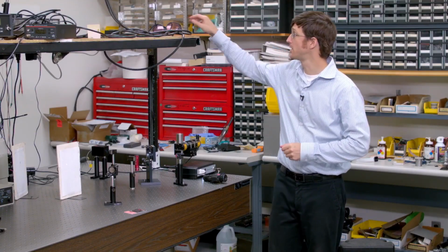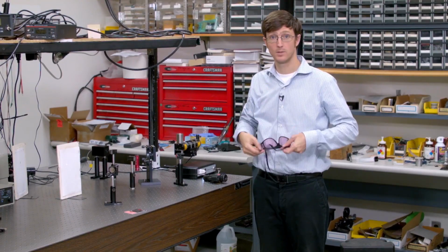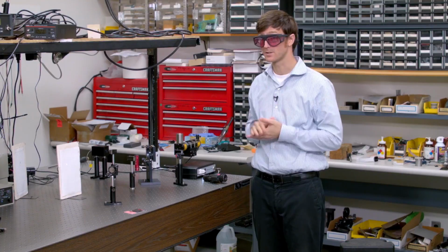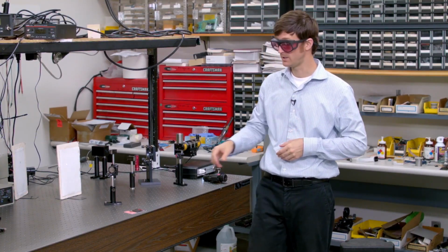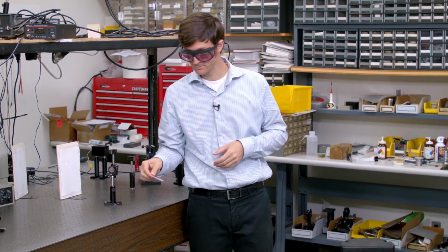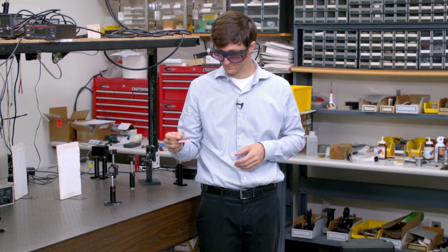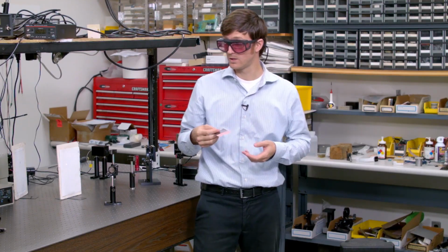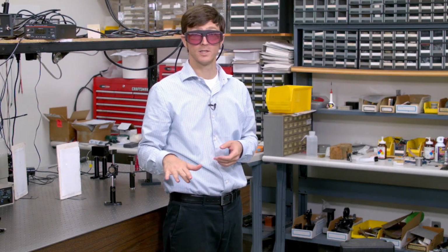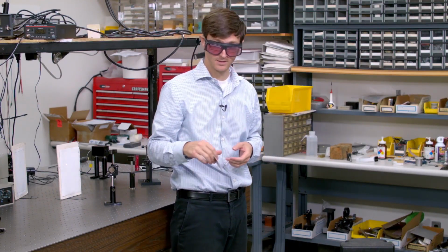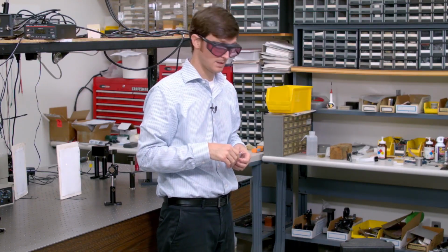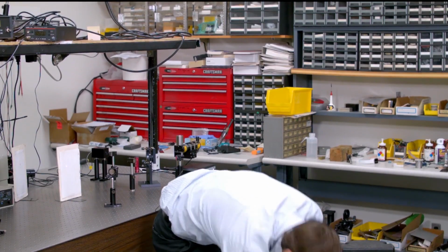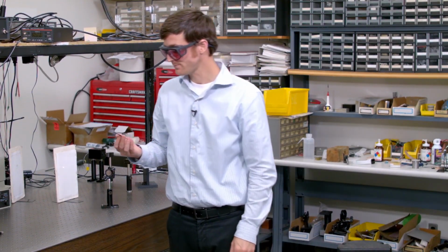So now we need to put on the goggles and repeat the process with a higher powered laser. Now because this is an invisible laser, we can't use an index card to trace the beam. Instead, we need to use an IR card. Whoops. This leads me to another point. When bending over, your eyes might cross the level of the laser beam. So it's a good idea to turn your back to the table and close your eyes on the way down and on the way up.